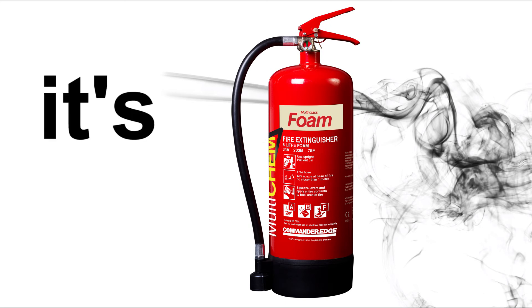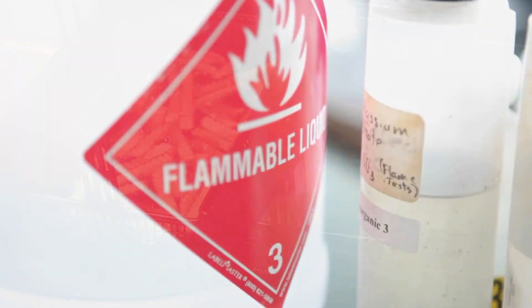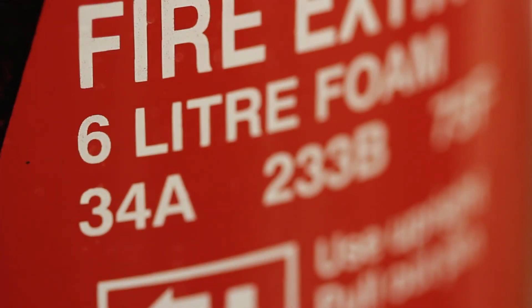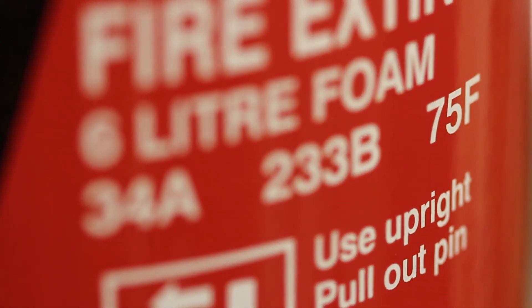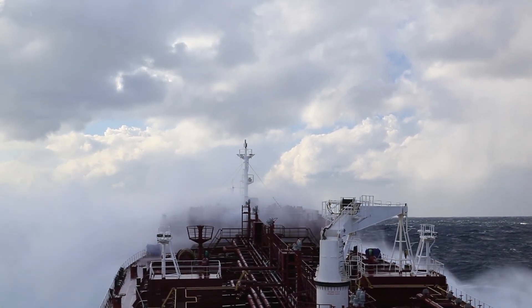Multichem — it's here. Being what's known as an ABF extinguisher, it can tackle class A fires, class B fires, and class F fires. And what is more, this unit has simply enormous performance, boasting a 34A233B75F fire rating. It also has a 35 kV dielectric test rating, making it safe for inadvertent use on live electrical equipment. And the MED ship's wheel approval makes it approved for marine applications too.